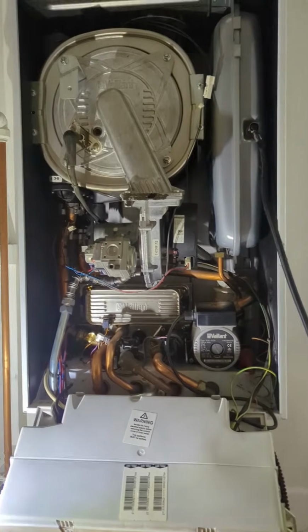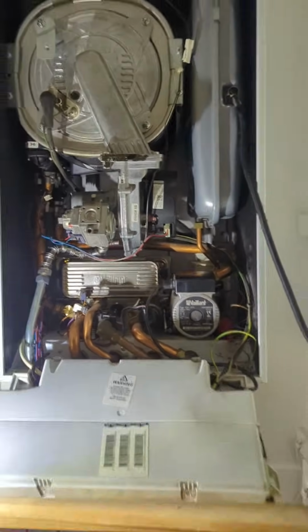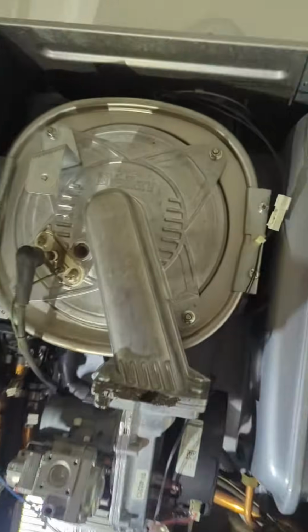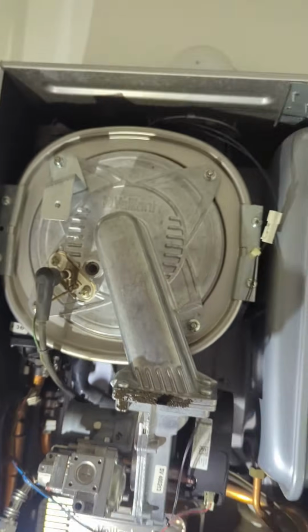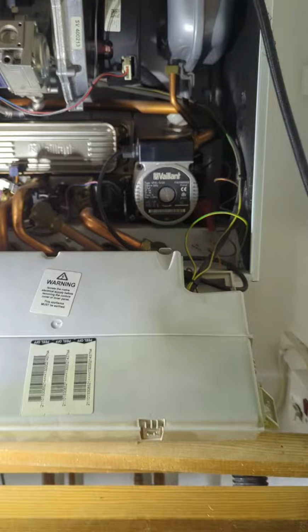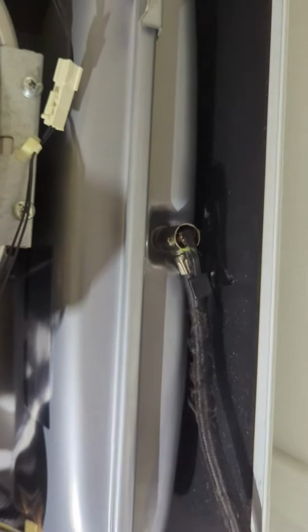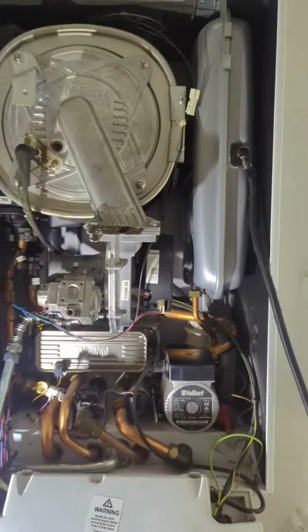So this is the annual service on the Vaillant combi boiler. This is the EcoTec Plus. The Plus has got the stainless steel heat exchanger. The boiler gets drained down and cleaned inside, and then we can recharge this part, which is called the expansion vessel. It should be done every year.